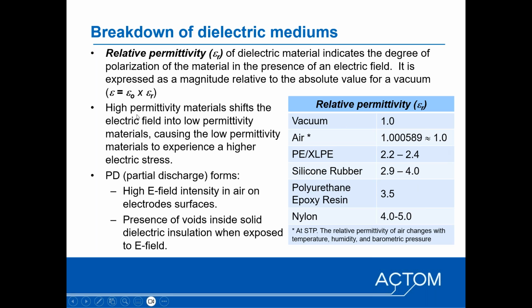when we do field plot simulations. So the effect of relative permittivity is that high permittivity materials tend to shift your electric field stress into the low permittivity materials. So if you've got epoxy and air next to one another, the epoxy with a higher permittivity would shift the electric field into the air. And that is what we will see when we look at partial discharge forming inside voids when we look at the dielectric material.